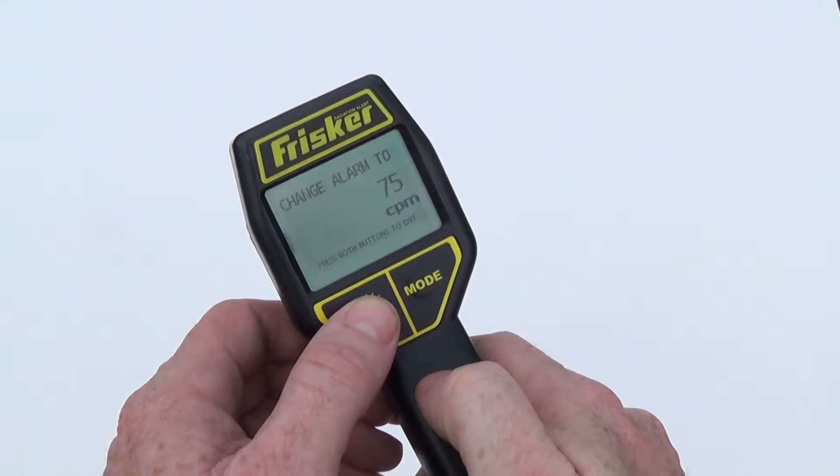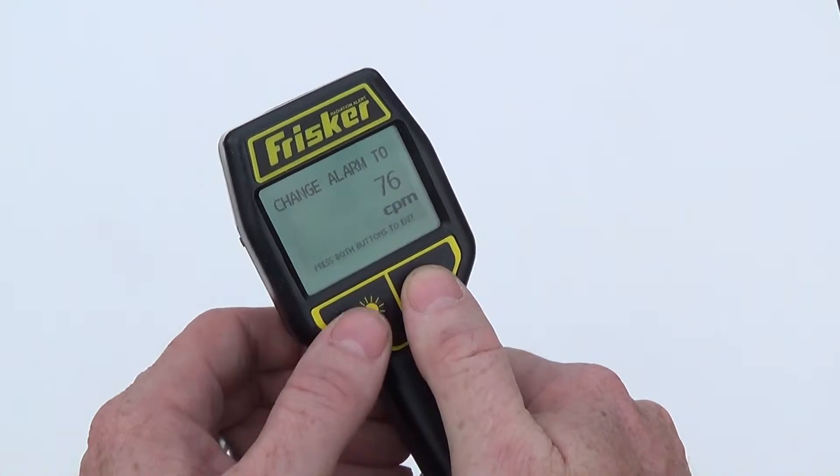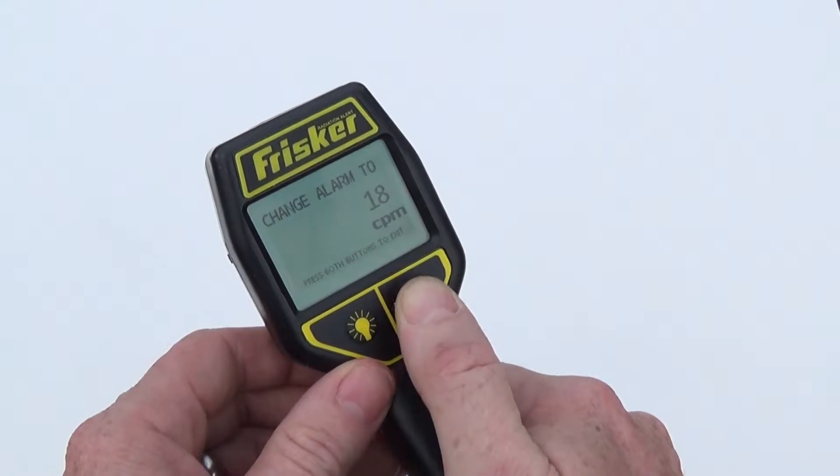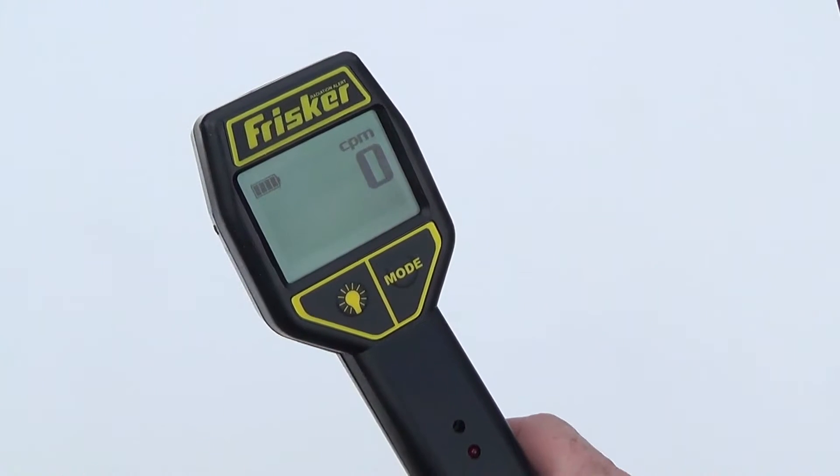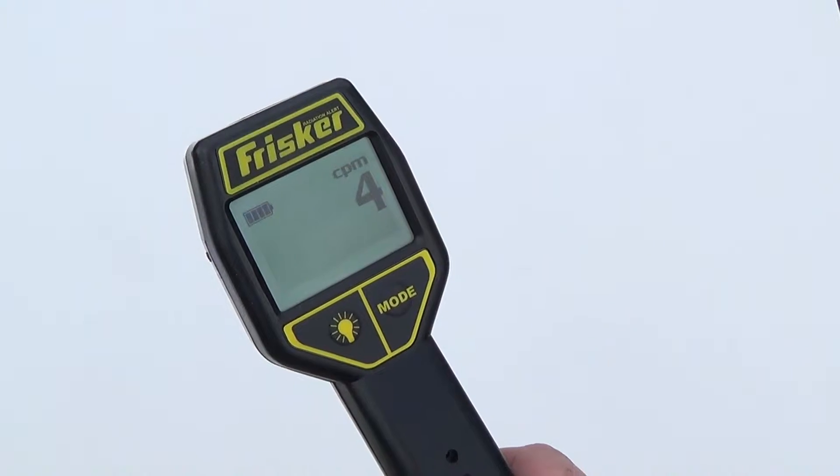Use the backlight button as the plus button to increase the set alarm level, and use the mode button as the minus button to lower the set alarm level. Once you have selected your desired alarm level, press both the backlight and mode buttons at the same time to exit the alarm set menu and resume normal operation of the radiation alert Frisker.